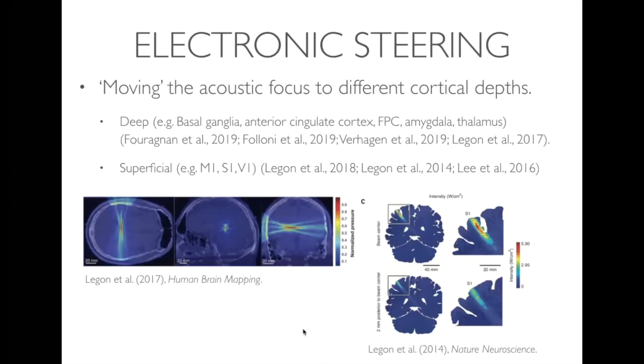Now we're going to cover the exciting bit of the webinar, which is how you can achieve cortical and subcortical stimulation with the same transducer using the NeuroFUS system. What it can do is electrically steer where the acoustic focus is, and that enables you to stimulate deeper sites as well as more superficial sites with the same transducer, without any calibration or lensing or things like that. That enables you to replicate all the cool stuff that's been done stimulating deep sites, as I mentioned previously, as well as superficial sites.